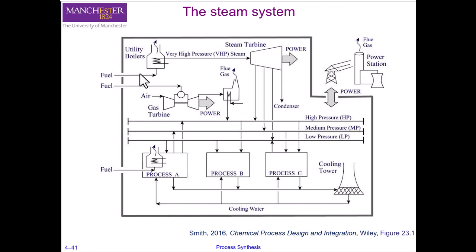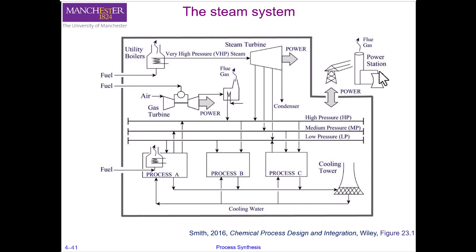Here is an overview of a site's energy utility systems. At the top left corner, you have a boiler that uses fuel and sometimes waste products from the process to convert water into steam. The steam is produced at very high pressure, but generally not used above 40 bar, largely because of the cost of piping systems for transporting steam at very high pressures around the site. The steam can be let down through a steam turbine, which can produce steam at different pressures — very high pressure, medium pressure, and low pressure steam. The power generated by the steam turbine can be used on site along with power imported from a power station.